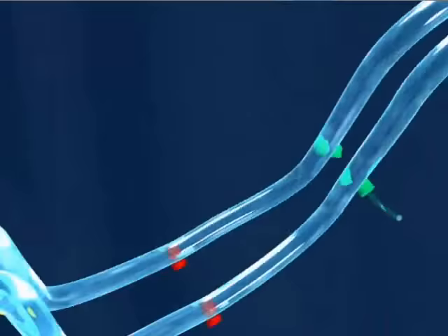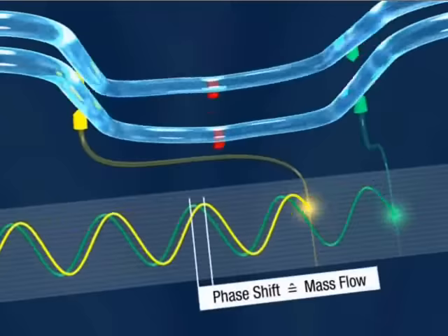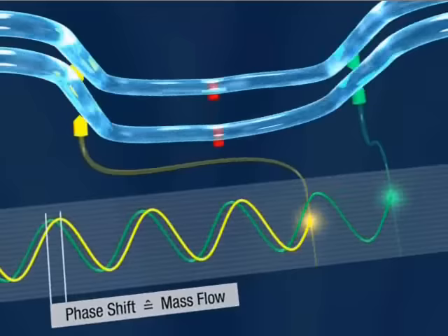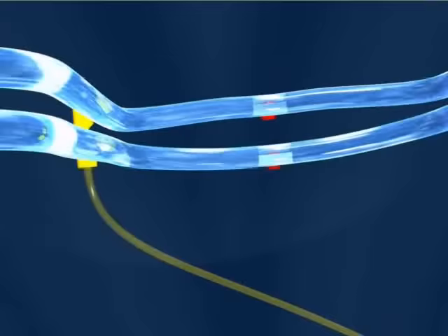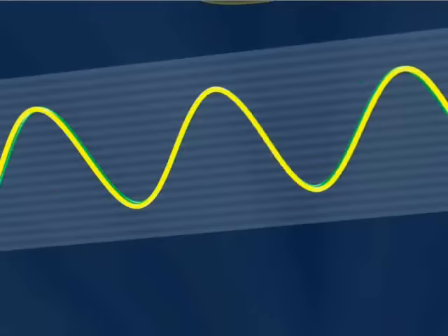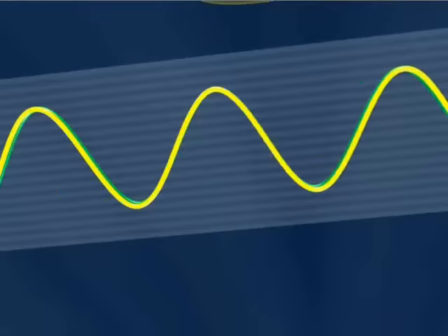A phase shift occurs between the first and the second sensor. The mass flow rate is derived from this phase difference. Should the density of the media need to be determined, it is simply computed by evaluation of the oscillation frequency of the measuring tubes.